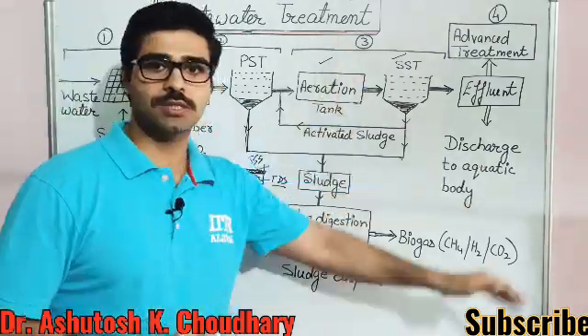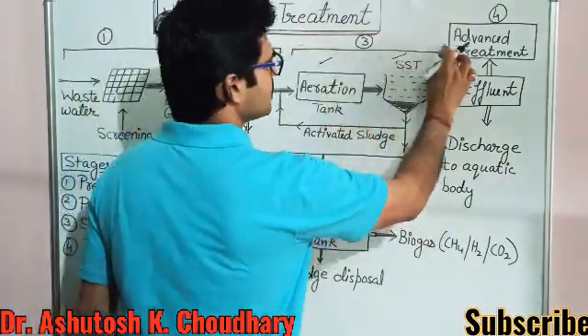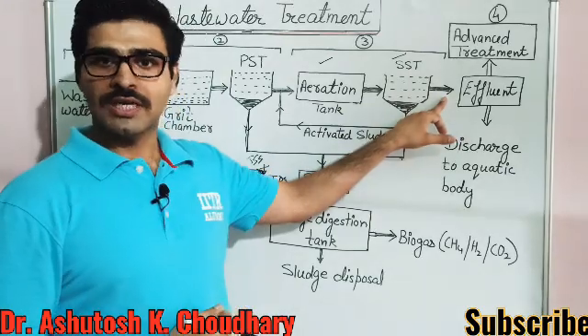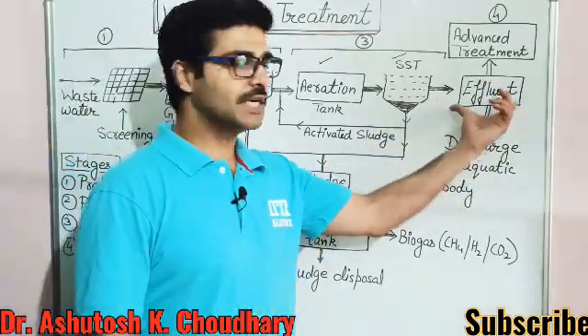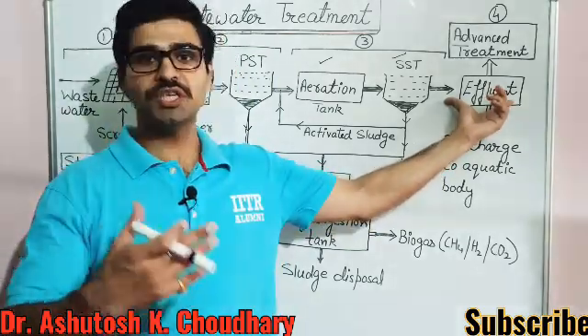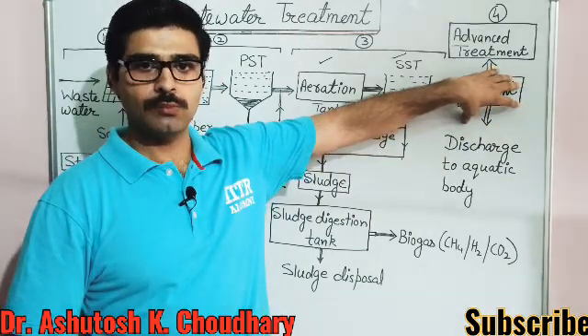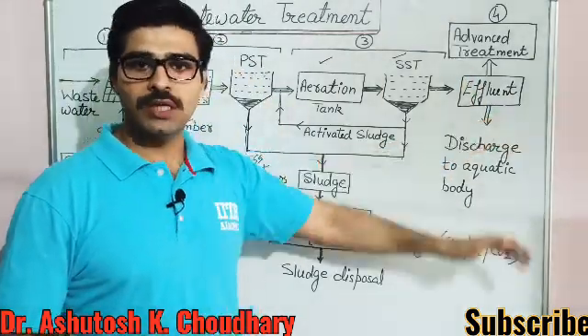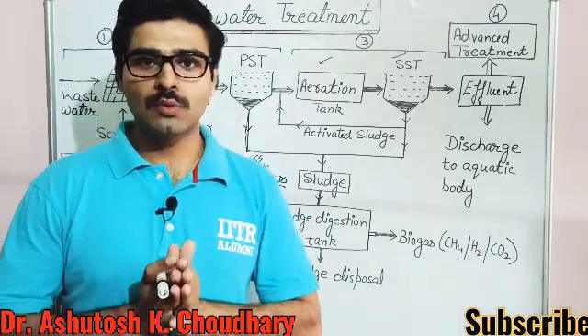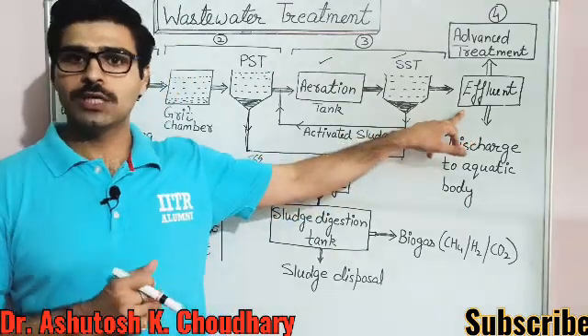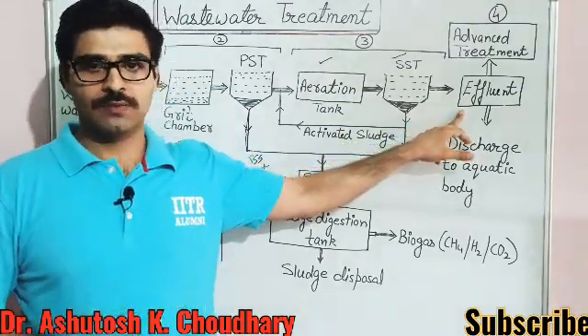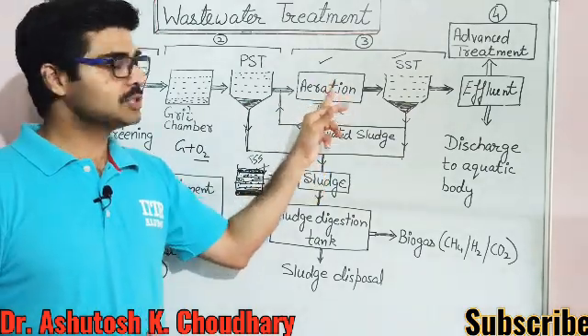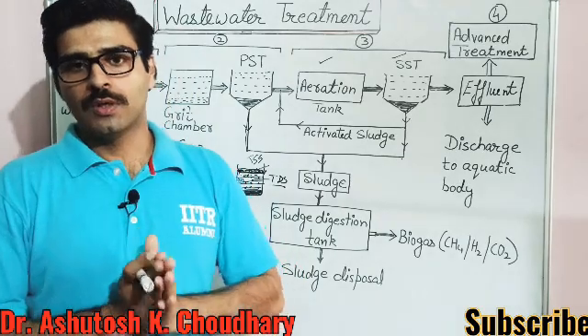After secondary treatment, the water we get is called effluent — the water we are going to discharge. Up to this stage, there is more than 90 percent removal of BOD, and total suspended solids are also removed by more than 90 percent. Some particles that are dissolved get oxidized by bacteria through this process.